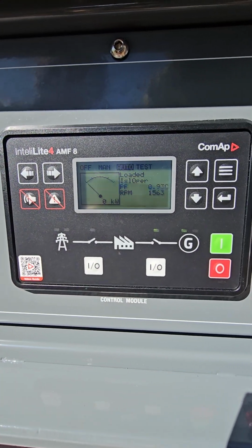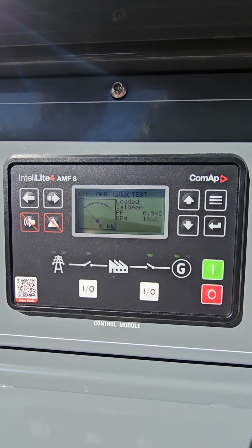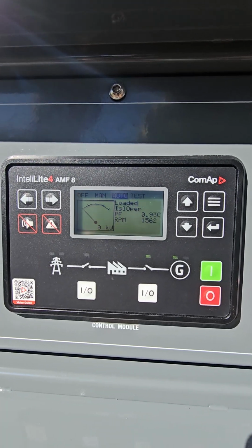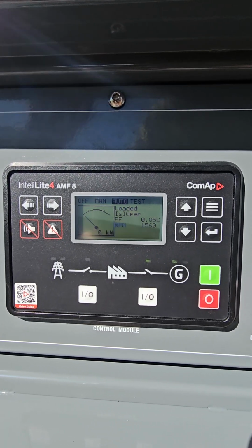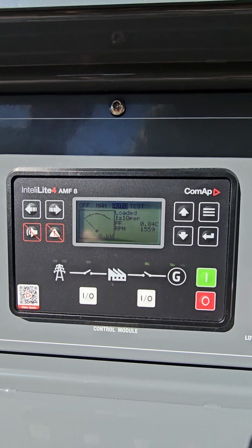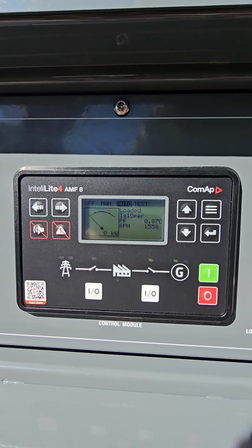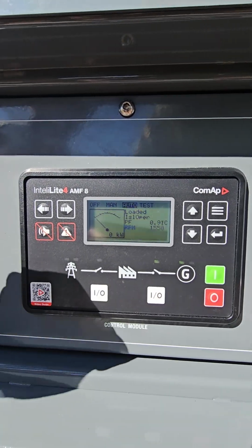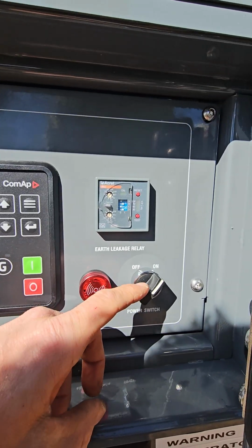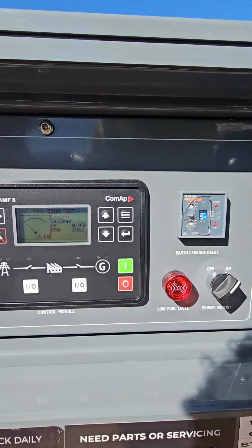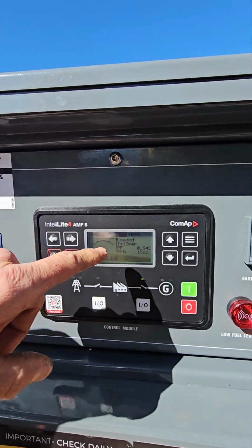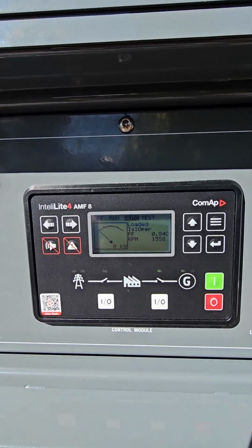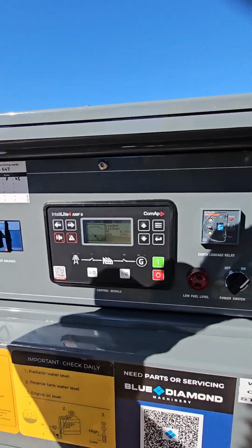We have a generator battery charger plugged in permanently so that the battery in the generator will stay at a nice level, and this display can stay on for as long as it needs to. So this display has to stay on. So this is your on switch for your display here. Leave that on. Make sure the breaker is on and make sure that's in auto. That's your normal way the generator should be at all times.